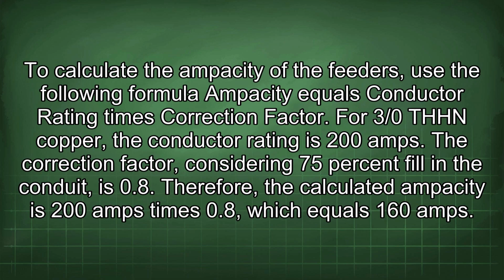To calculate the ampacity of the feeders, use the following formula: ampacity equals conductor rating times correction factor. For 3/0 THHN copper, the conductor rating is 200 amps. The correction factor, considering 75% fill in the conduit, is 0.8. Therefore, the calculated ampacity is 200 amps times 0.8, which equals 160 amps.